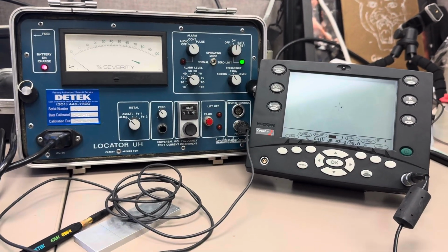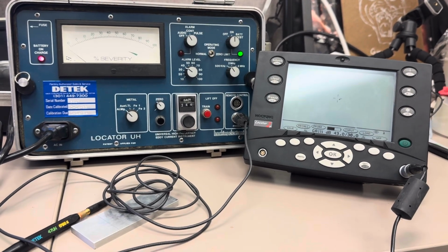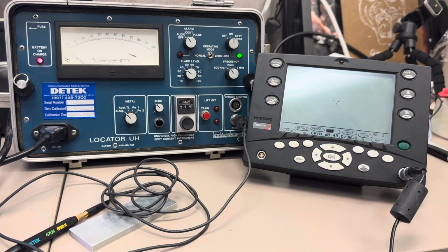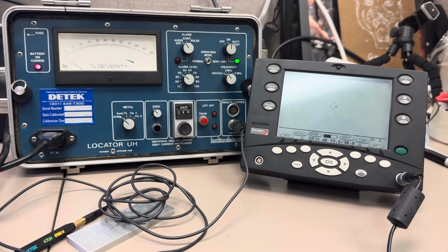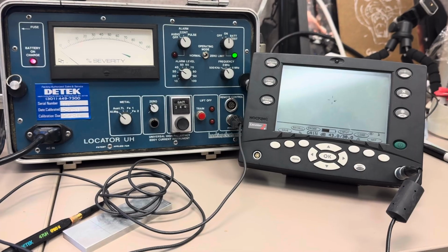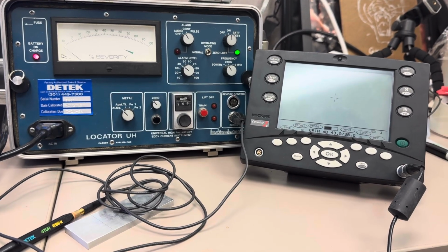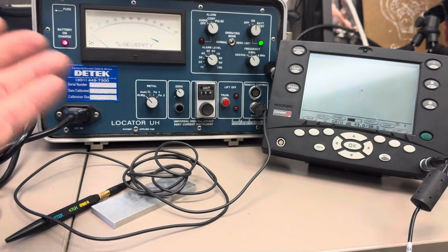Now, what about this locator over here? That's also a non-calibrated display. That doesn't mean the instrument failed its annual calibration. It just means that it's not set up for any particular test, giving the operator the flexibility to test for a variety of things. And you can do that on either one of these testers.